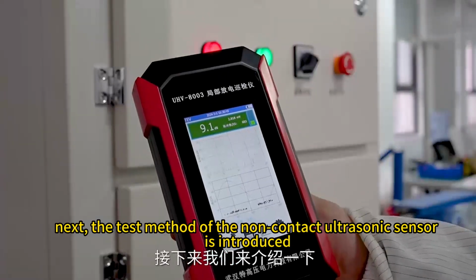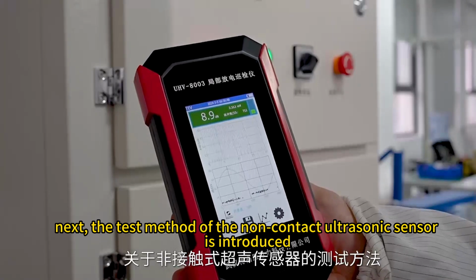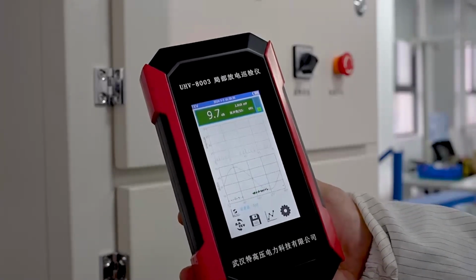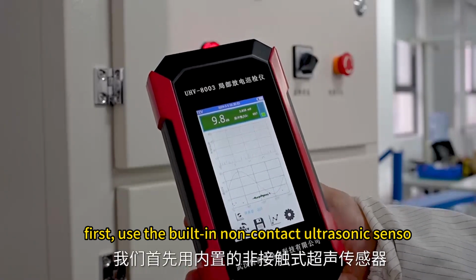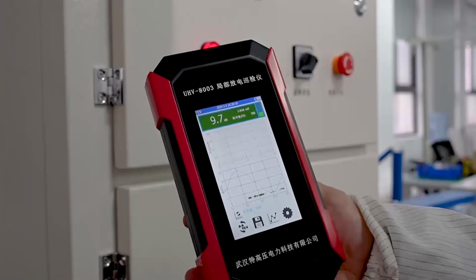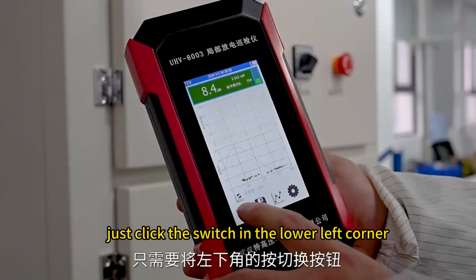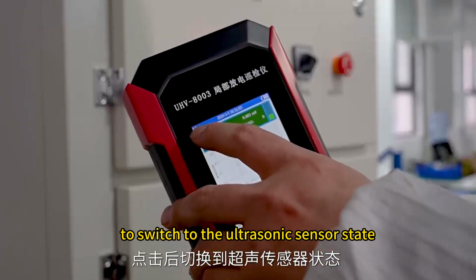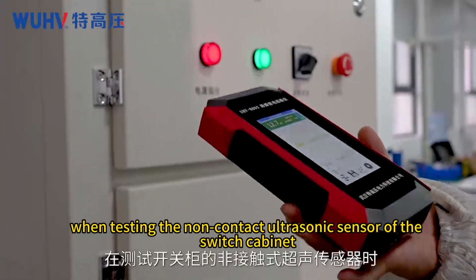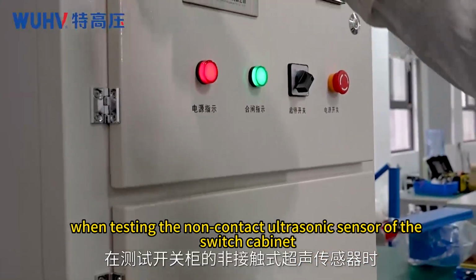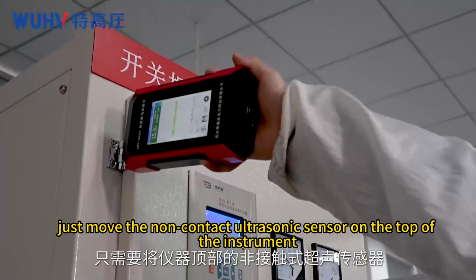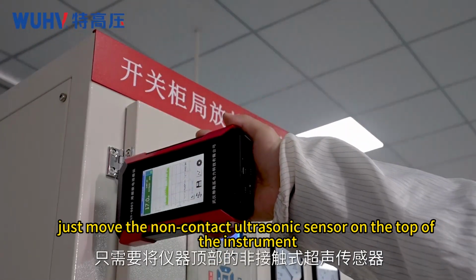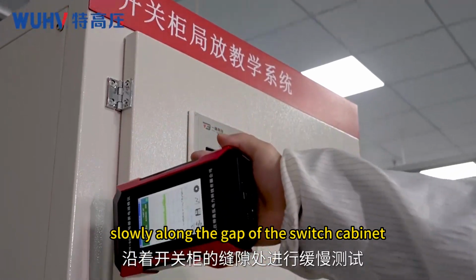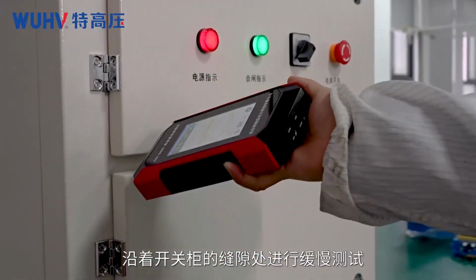Next, the test method of the non-contact ultrasonic sensor is introduced. First, use the built-in non-contact ultrasonic sensor. Just click the switch in the lower left corner to switch to the ultrasonic sensor state. When testing the non-contact ultrasonic sensor of the switch cabinet, just move the non-contact ultrasonic sensor on the top of the instrument, slowly along the gap of the switch cabinet.